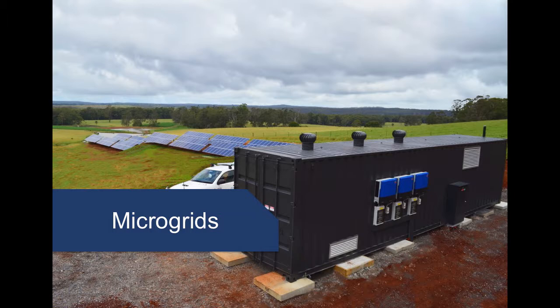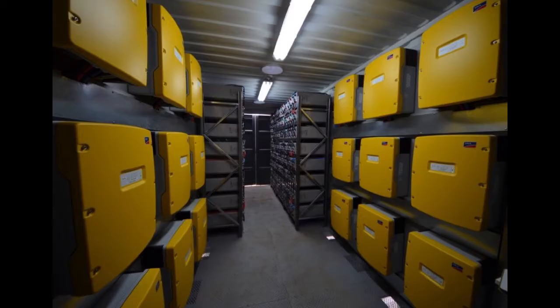That was a microgrid system we did up in New South Wales. That's the interior of the system. Each of these battery inverters has about an 8 kilowatt half-hour rating, and there were 18 of them, so about 140 kilowatts of power, half-hour rating, that can be delivered from the batteries to the loads on that property.